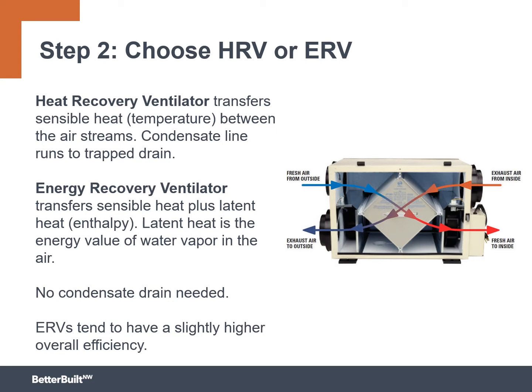An energy recovery ventilator, on the other hand, transfers that sensible heat, or the temperature, plus what we call latent heat, or enthalpy. It's another way of saying the energy that is also involved in moisture movement. So latent heat really is the energy value of water vapor in the air. One of the benefits of an energy recovery ventilator is you don't need a condensate drain. And they do tend to have a slightly higher overall efficiency. If there's a challenge to ERVs, it's that they may cost a little bit more. Depending on the brand, for some the cost is very similar between their HRV and their ERV. For others, the cost is higher for the ERV.